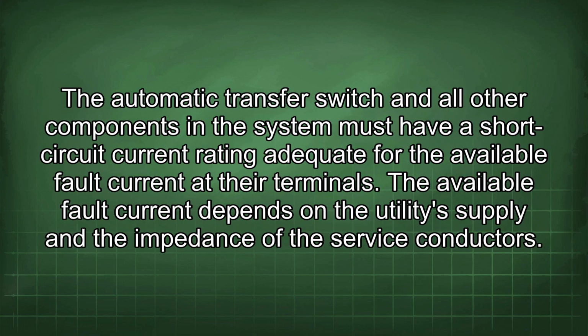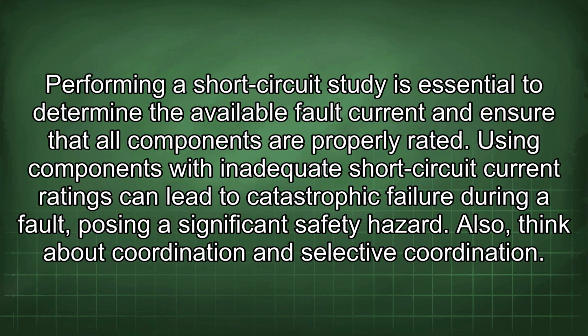The automatic transfer switch and all other components in the system must have a short circuit current rating adequate for the available fault current at their terminals. The available fault current depends on the utility supply and the impedance of the service conductors. Performing a short circuit study is essential to determine the available fault current and ensure that all components are properly rated.